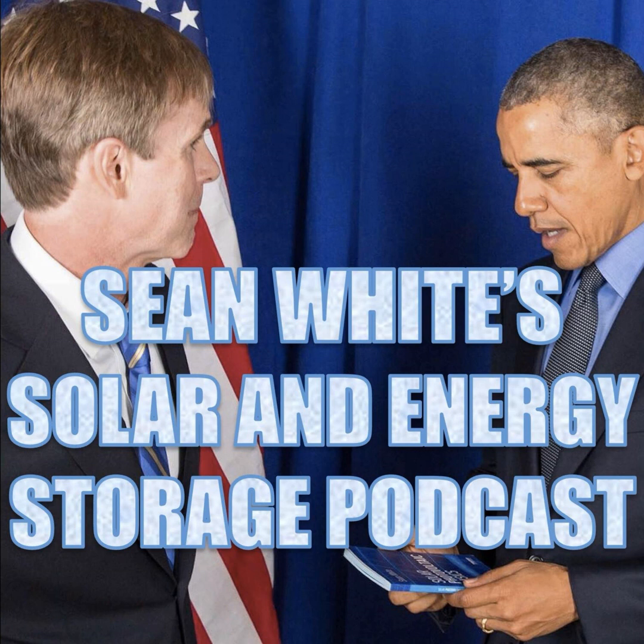There's lots of different reasons why grounding is done in different ways. Sometimes the earth is more conductive in certain places than others. Sometimes you worry about lightning bolts. Sometimes you worry about electrical wires falling down from high voltage equipment. Sometimes you ground fences and large utility scale photovoltaic systems. So, hey, get grounded.